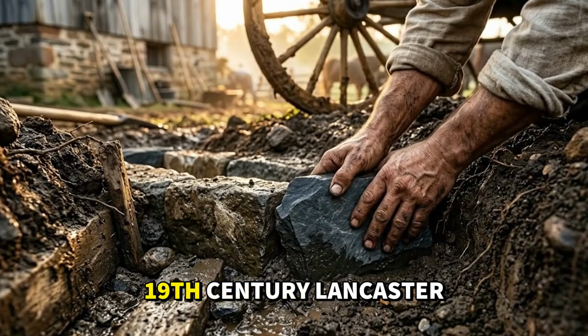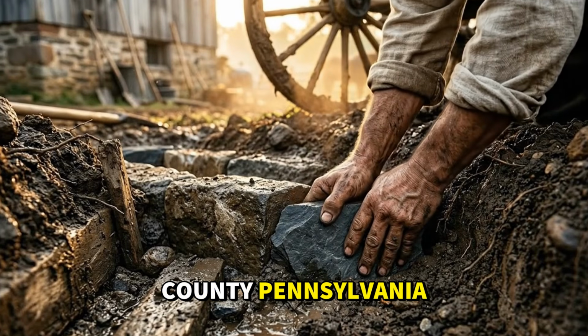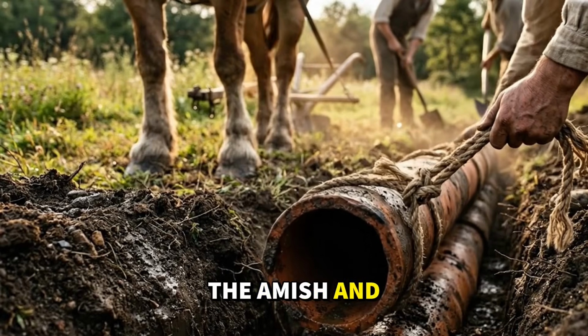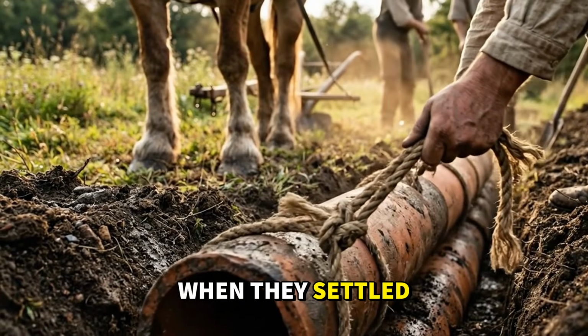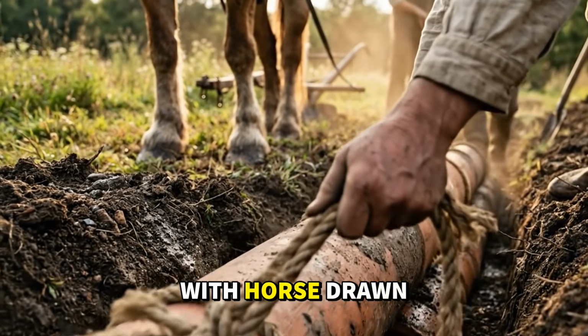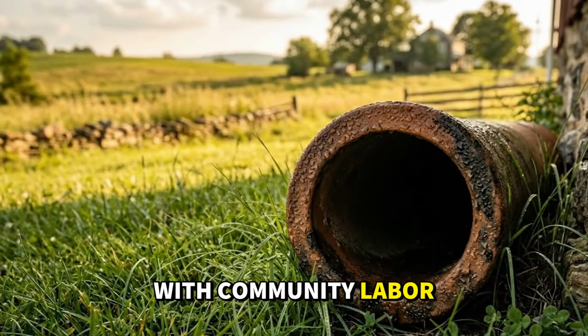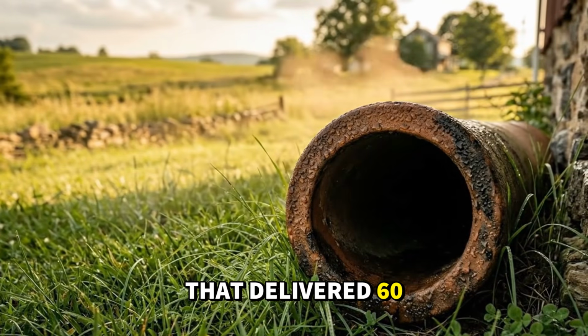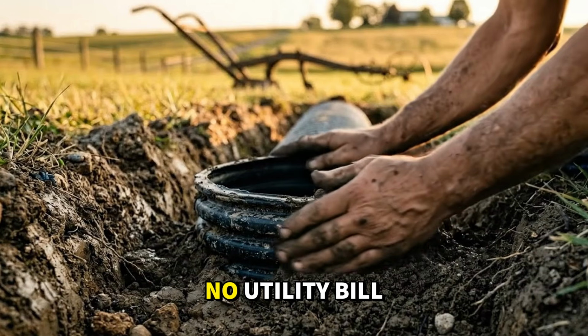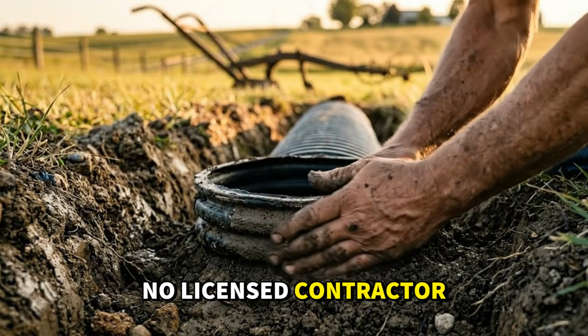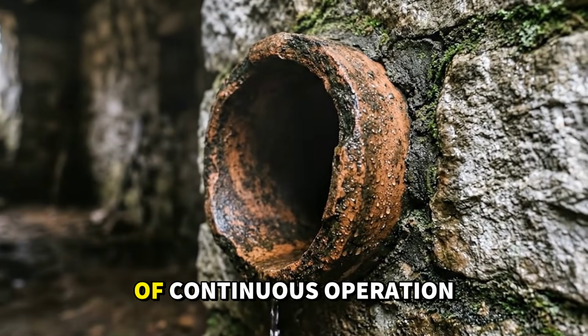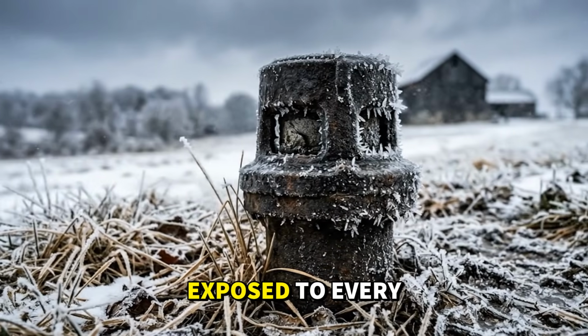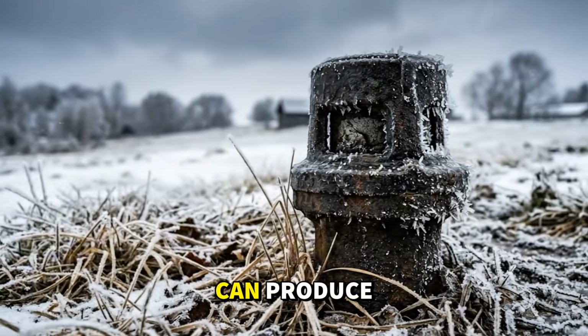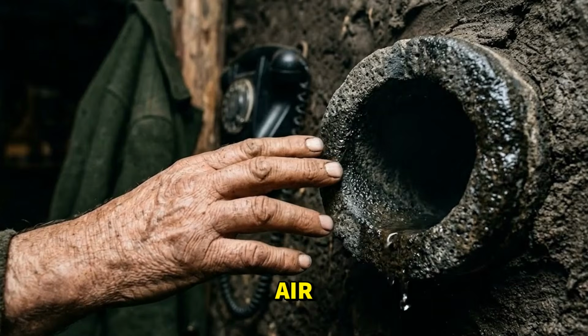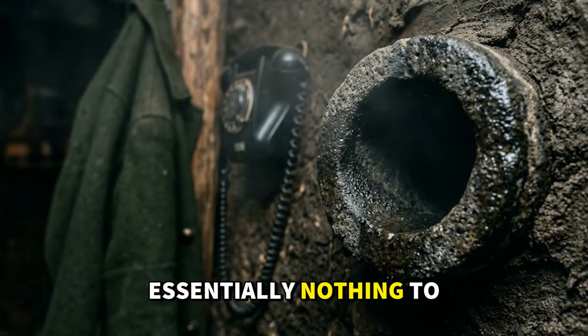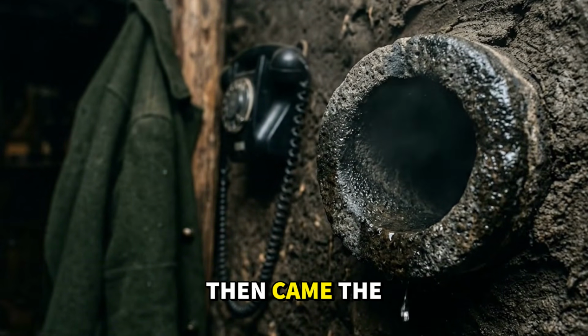Now jump forward. 19th century, Lancaster County, Pennsylvania, Holmes County, Ohio. The Amish and Mennonite communities adopted earth tube cooling when they settled in North America. They dug trenches with horse-drawn equipment. They laid pipe with community labor. They built systems for a few $100s that delivered 60-degree air in July. No grid connection, no utility bill, no licensed contractor. Those systems are still running, over a century of continuous operation in some cases. Exposed to every weather extreme Pennsylvania and Ohio can produce, still delivering cooled air, still maintained by hand, still costing essentially nothing to operate.